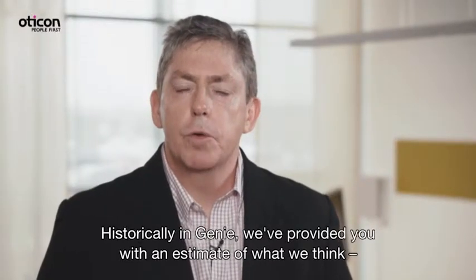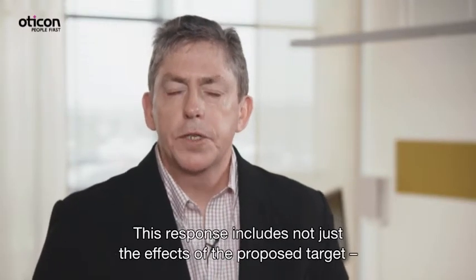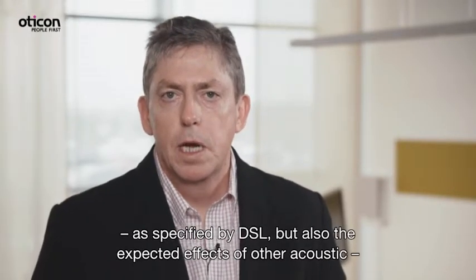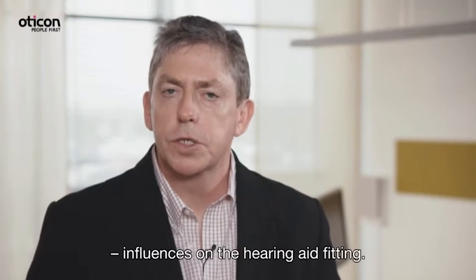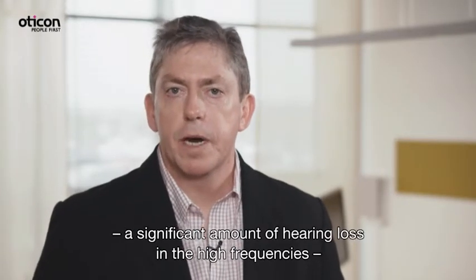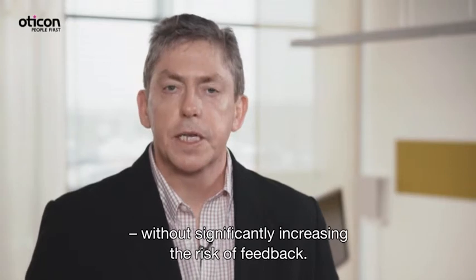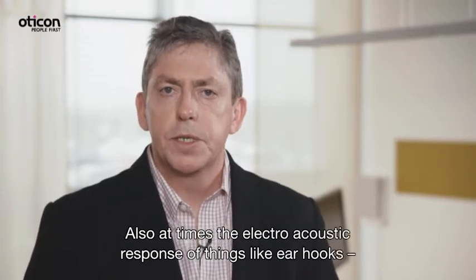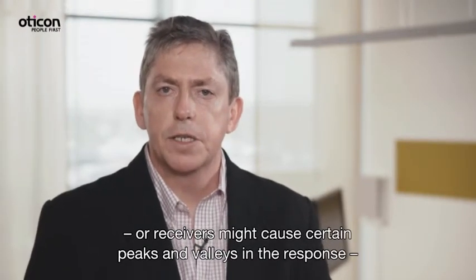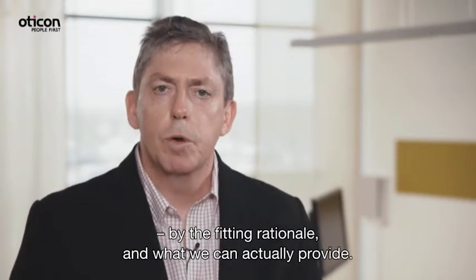Historically in Genie, we've provided an estimate of what we think the hearing aid should be providing on the child's ear. This response includes not just the effects of the proposed target as specified by DSL, but also the expected effects of other acoustic influences on the fitting. For example, if the hearing aid is fit to an open vent, or if there's significant hearing loss in the high frequencies and we simply cannot provide the gain called for by the fitting rationale without significantly increasing the risk of feedback. Also, the electroacoustic response of ear hooks or receivers might cause certain peaks and valleys in the response, leading to slight mismatches between what is proposed by the fitting rationale and what we can actually provide.